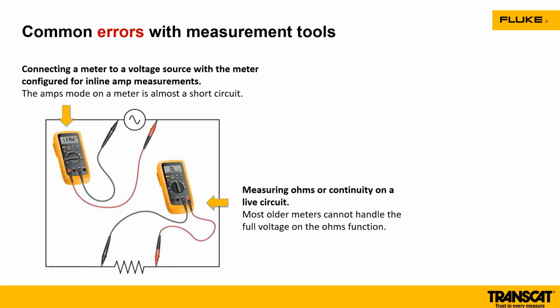So let's just quickly look at the meter aspect of it. When you're connecting your meter and you're going from voltage, you should be able to get that measurement. But some of the older meters, if you were in the ohms or continuity position, they couldn't handle the voltage. They would actually create a short within the meter and cause that fault. So we want to make sure that you have the right meter when you're making these types of measurements. And if you have the meter accidentally in the wrong position, the meter can still safely get out of that, not causing that arc flash or all of that.